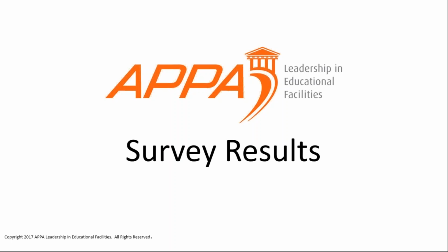When I was in Illinois, there was an Illinois OSHA that we had to comply with, but the standards are pretty much the same. More specifically, and consistent with what I was saying in the presentation, you can use tagout only if you can't already do lockout. For instance, a piece of equipment that doesn't have an appropriate lockout control mechanism, or one that can be locked out by putting a hasp or a lock through a set of holes, you have to use lockout if that exists. If it doesn't exist, then you have to tag it out, and your procedures have to provide the same protection for the employees doing the work as if it had a lockout on it. So I think everything is consistent.